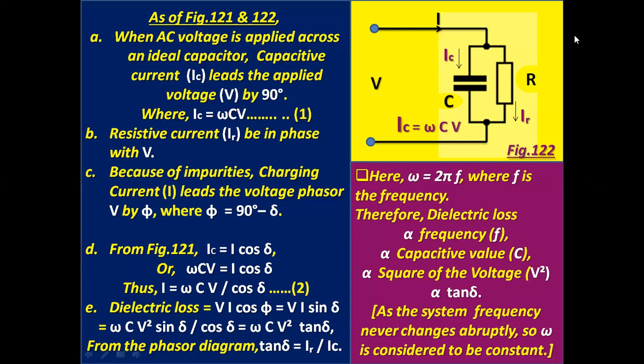From figure 121, IC equals I cos delta, or IC equals omega CV, that is omega CV equals I cos delta. Thus, I equals omega CV by cos delta. Dielectric loss equals VI cos phi equals VI sin delta, because phi is 90 degree minus delta. That is omega CV square sin delta divided by cos delta, which means omega CV square tan delta.